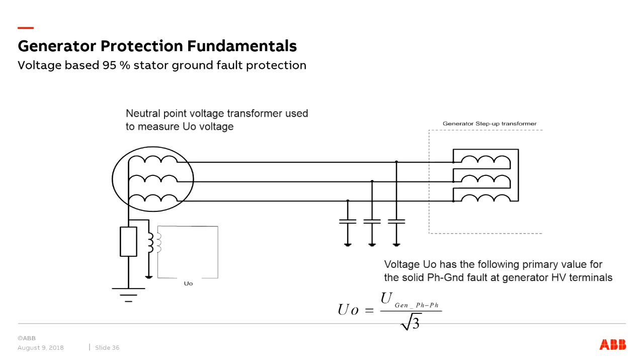So here is where the ground fault measurement is done by measuring the residual voltage from a voltage transformer connected between the generator neutral point and the ground, and the residual voltage is equivalent to the open delta connected phase voltage transformers. Here, one possible disadvantage of using the neutral point voltage transformer is that the voltage transformer can have a winding interruption undetected, as the neutral point voltage is normally zero. So this is how we measure that.